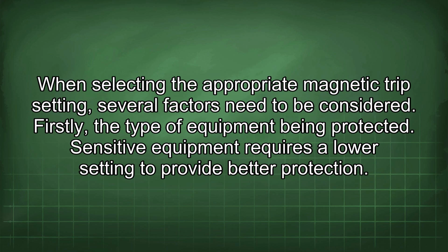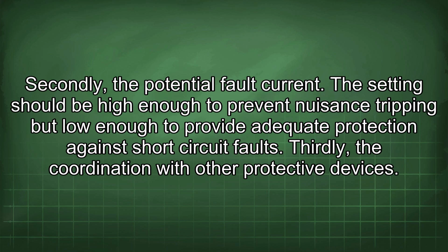When selecting the appropriate magnetic trip setting, several factors need to be considered. Firstly, the type of equipment being protected. Sensitive equipment requires a lower setting to provide better protection. Secondly, the potential fault current. The setting should be high enough to prevent nuisance tripping but low enough to provide adequate protection against short-circuit faults.